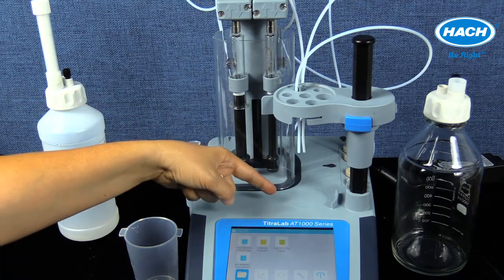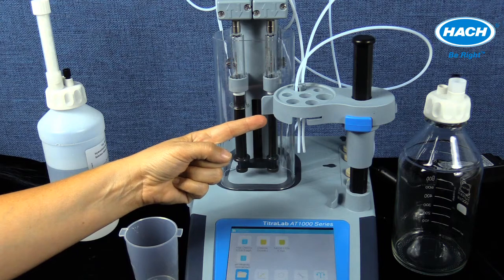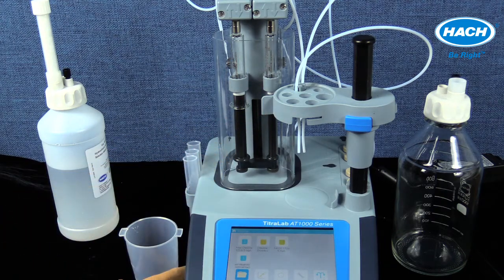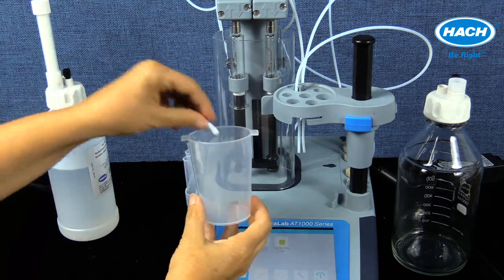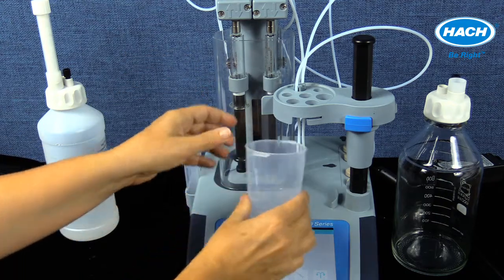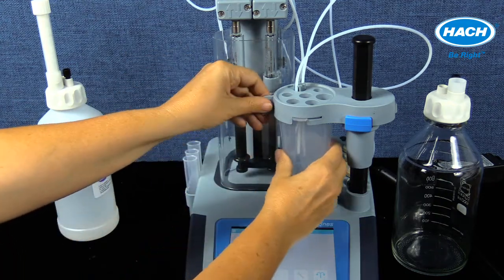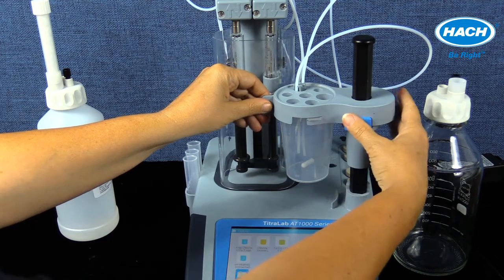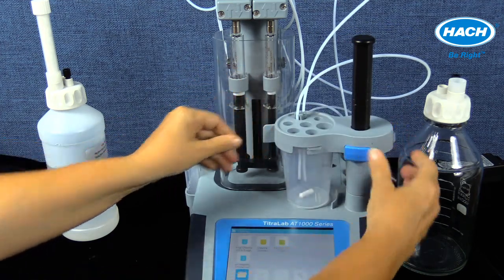Stirring the sample during the titration is very important for accuracy. The AT1000 has a built-in stirrer and sensor holder. The sensor holder accommodates a sample beaker with a stir bar that can lock into place and has holes to position the electrode and tubing in the correct orientation.